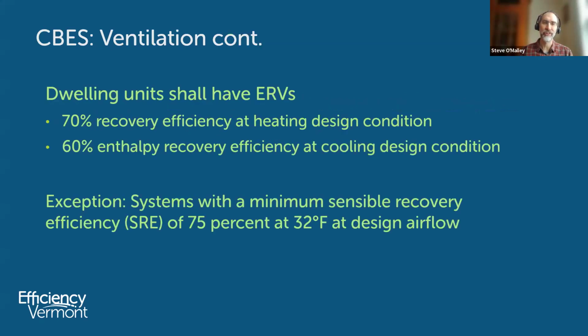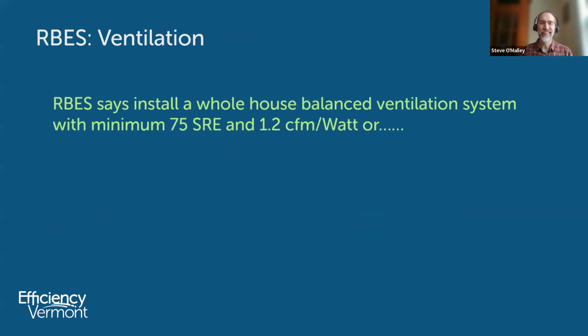If I go back to the CBES ventilation and look at a 70% recovery efficiency for an ERV, that to me is what makes sense in terms of available equipment and not breaking the budget to get balanced ventilation in our building. So I don't have a great answer for you on that one. Maybe that ends up being something we, the design community, meaning the architects, mechanical engineers, et cetera, collectively do: if we have an RBES building, we write to the Department of Public Service to say, hey, it's a very large piece of equipment, we're installing a 70% efficient piece of equipment, is that going to be acceptable? And ask for a variance. That's how I think we should probably play that out.